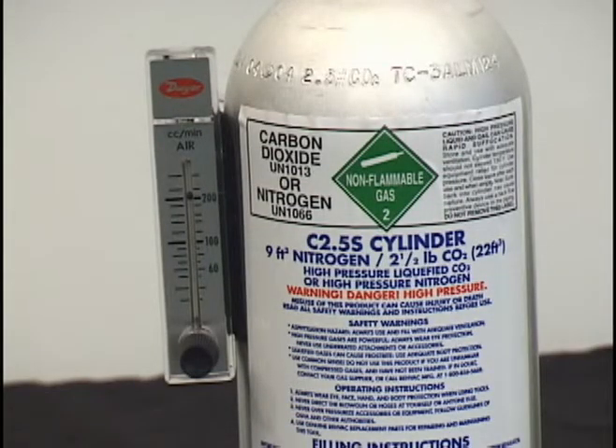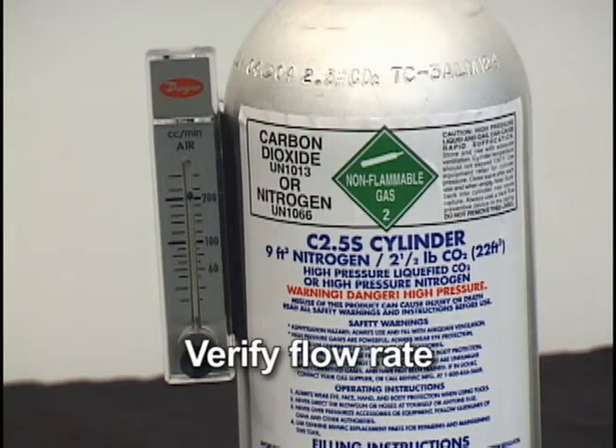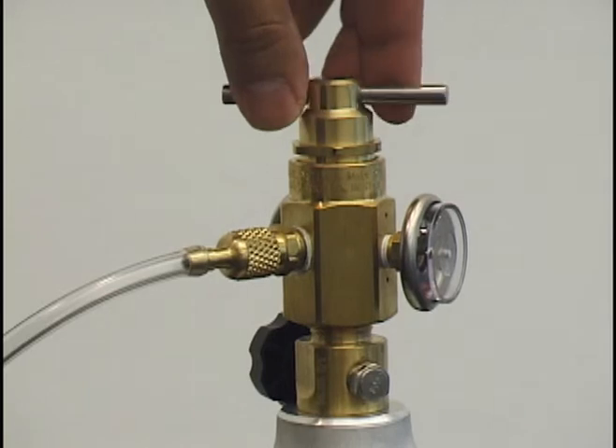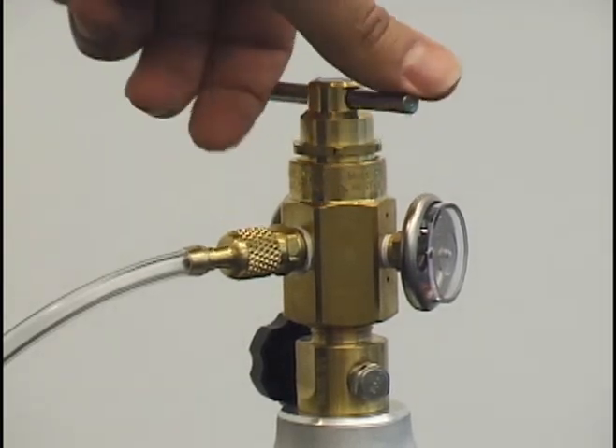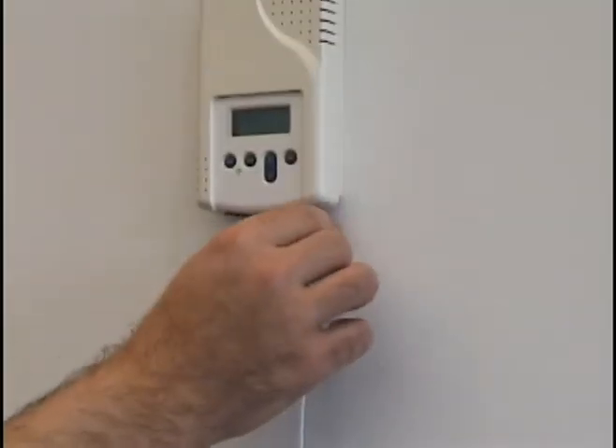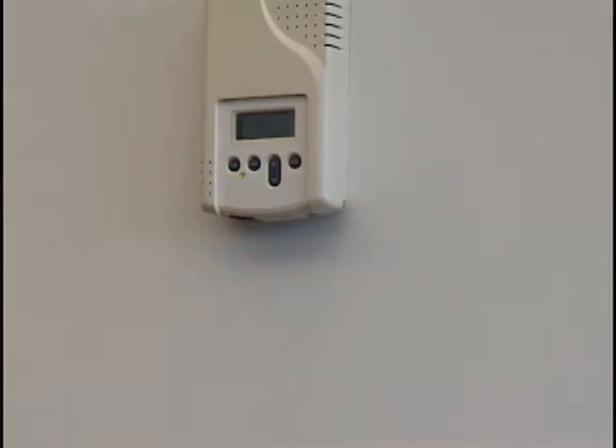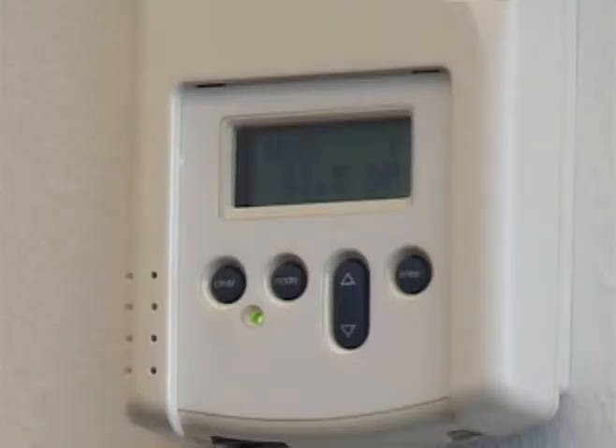Step 3. End calibration. To complete the calibration procedure, first verify the gas flow is still at approximately 200 cc's per minute. If the flow rate has dropped below 150 cc's per minute, calibration needs to be repeated from the beginning. If the flow rate is at approximately 200 cc's per minute, turn off the calibration gas and disconnect the tubing from the sensor. Verify that the display returns to the ambient dew point reading.